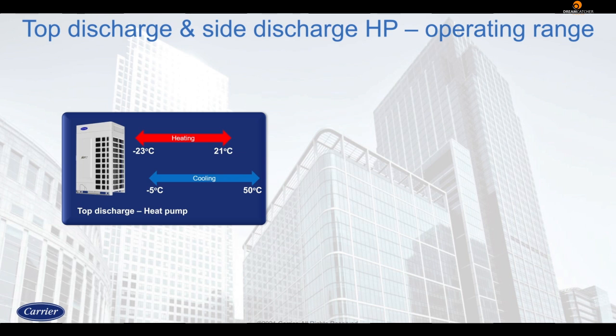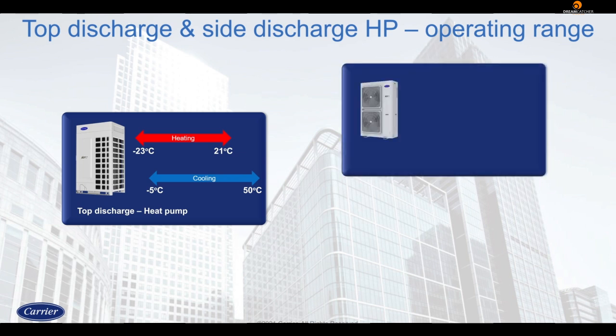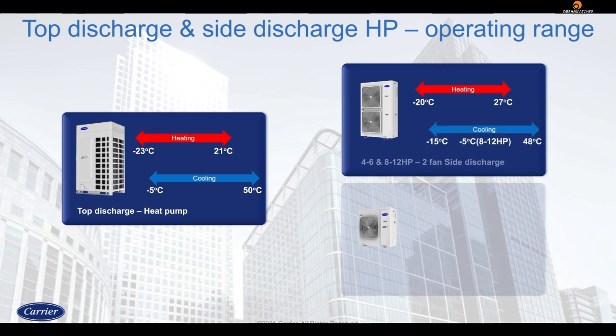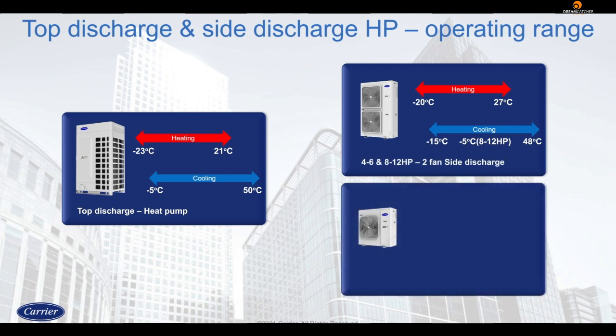Side discharge models also offer a wide operating range for both cooling and heating operations. 4 to 6 HP two-fan chassis cooling operating range from -15 degrees Celsius to 48 degrees Celsius, and 8 to 12 HP two-fan chassis from -5 degrees Celsius to 48 degrees Celsius. You may refer to different operating range of different side discharge models.